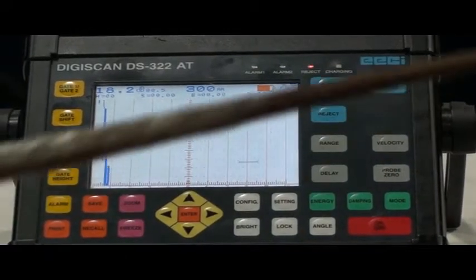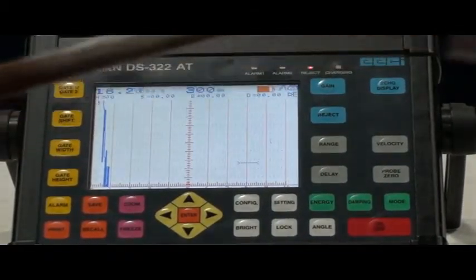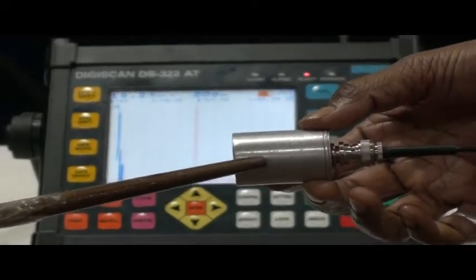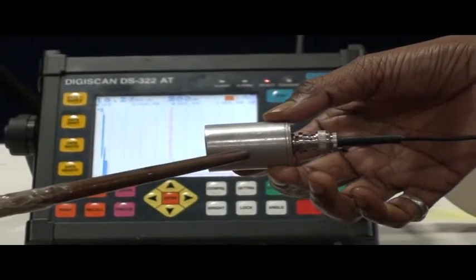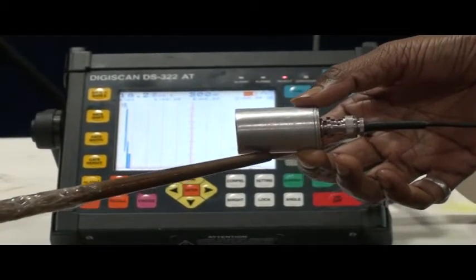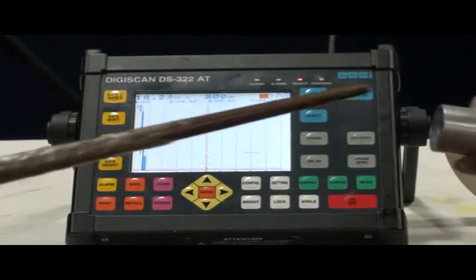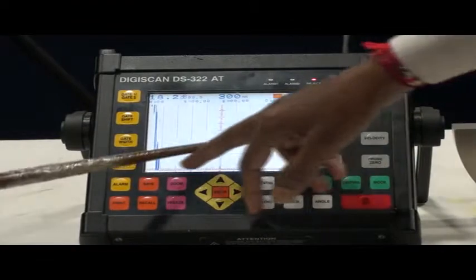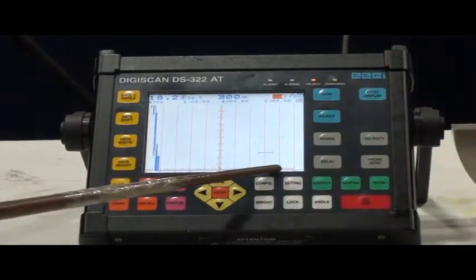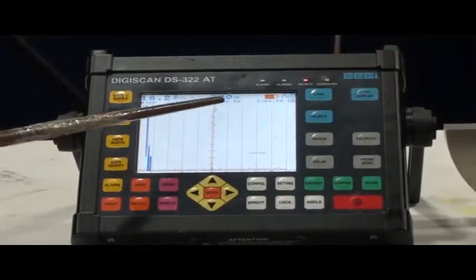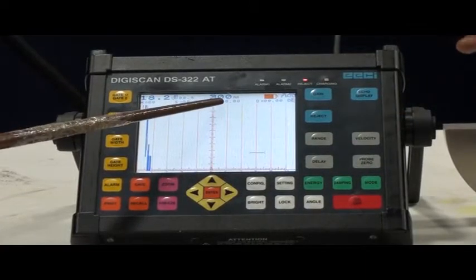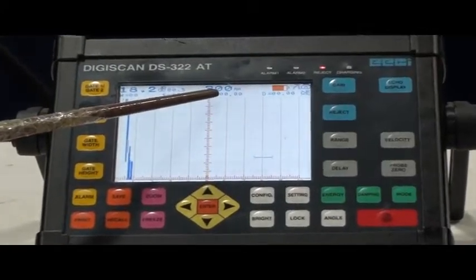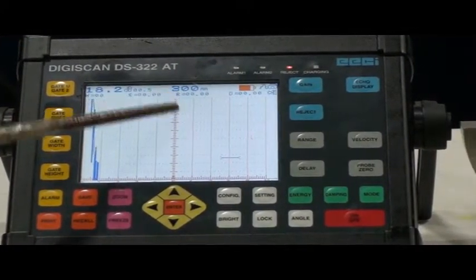To check the linearity of amplification, we have to use the zero-degree single crystal probe at 2 or 2.5 megahertz. Our purpose is to generate 4 to 5 echoes minimum on this screen, so we have to take a range from 100 to 500. Here we have taken the range and we will place this probe at this location.